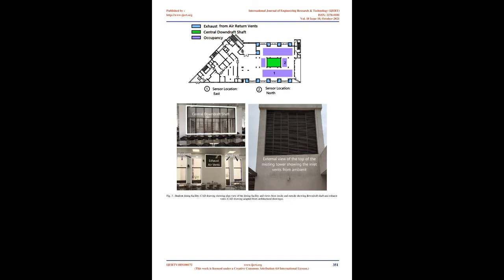However, there are a number of factors worth noting here that became apparent to us upon adoption and daily usage of these systems. The student dining facility being a large, approximately 500 sqm area per hall, and public space with transient usage, a typical user spends 20 to 30 minutes in the facility per meal, and a relatively simplistic design, the cooling provided by the PDEC system was found satisfactory by most users. The almost 4 degrees Celsius drop in temperature is readily perceivable by the users, particularly when observing the difference between on days and off days.